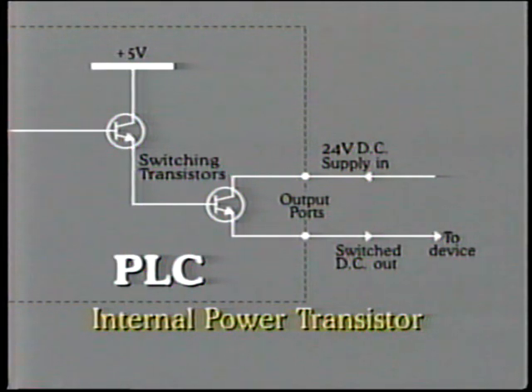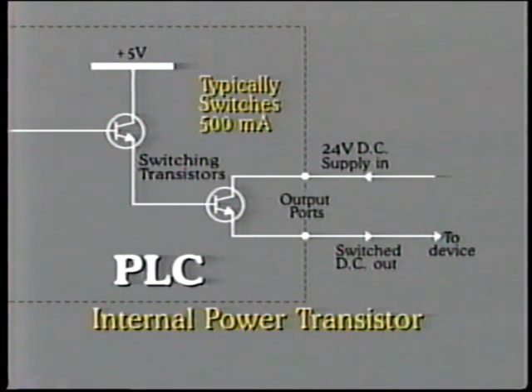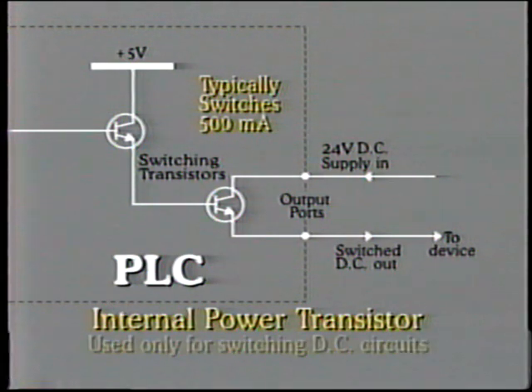And therefore, if the load device requires greater capacity, a power transistor will have to be installed adjacent to the load. In some PLCs, power transistors are built internally, so each of the output terminals is capable of switching higher current flow, typically 500 milliamps at 24 volts DC. In this arrangement, the 24 volts DC is obtained from the load device. Note that the transistor is used only for switching DC circuits.